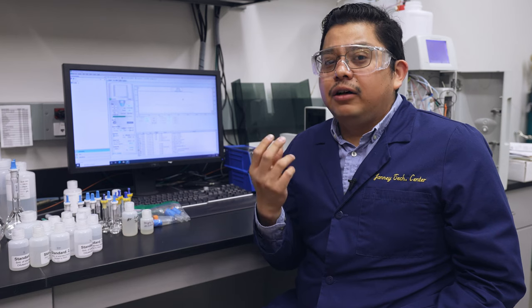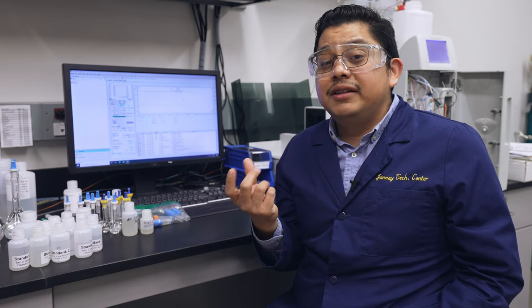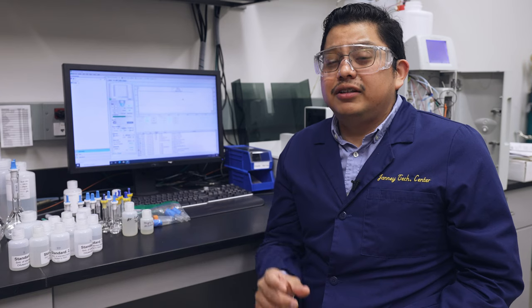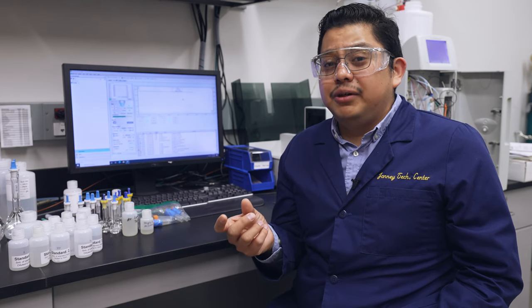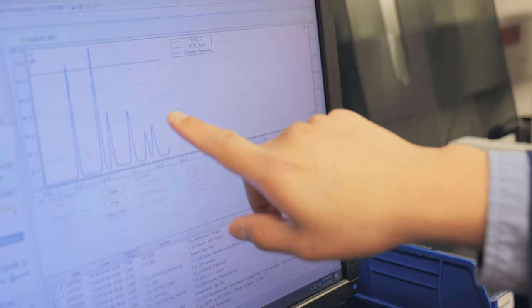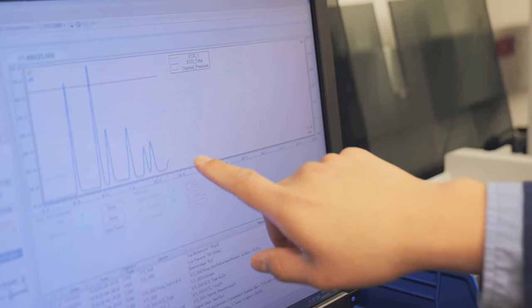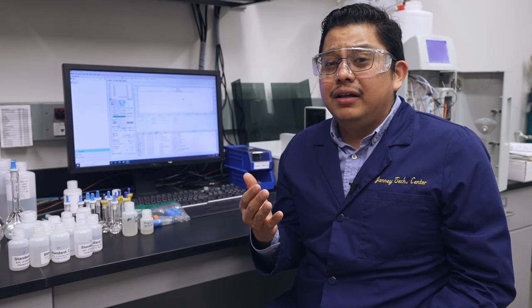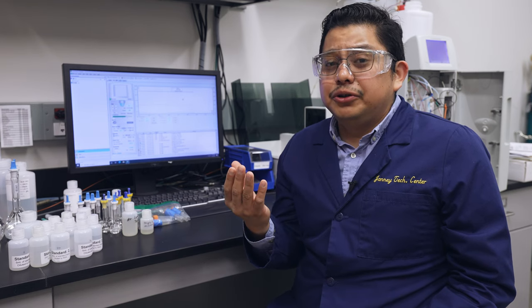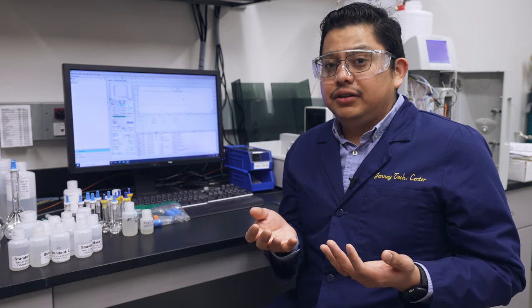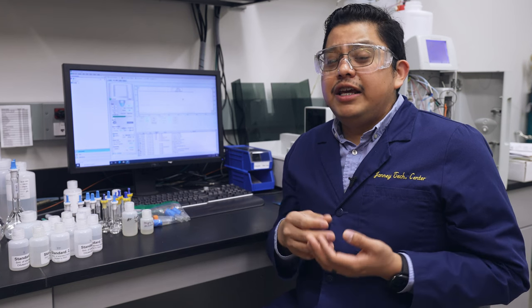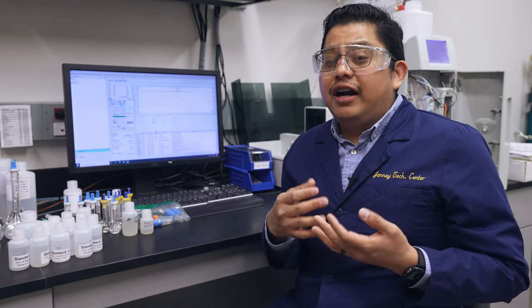As they exit the column they arrive at our conductivity detector. The conductivity detector measures the conductivity of the solution passing through it at that point in time, then plots this conductivity as a function of time. The resulting graph, or chromatogram, can allow us to quantify the ions in the solution. We can put all this information for the samples together with the information for our standards to generate accurate quantification curves for all our ions.